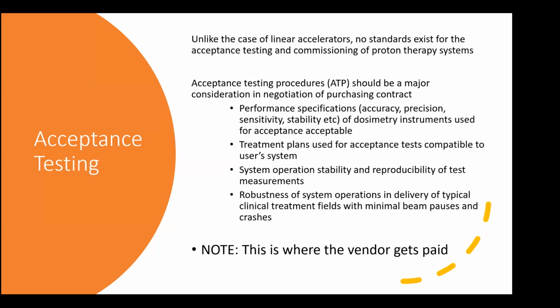the system. So this acceptance test procedure is you as the hospital. And maybe just say something that I usually say when I give talks at like a PTCOG or such, and usually I say this to kind of upset the vendors purposely: the vendor, whoever the vendor is, whether it's a vendor that has 1,000, 10,000 linear accelerators or some proton machines, or whether it's a new vendor that has one proton machine. For the most part, they've never actually treated a patient.